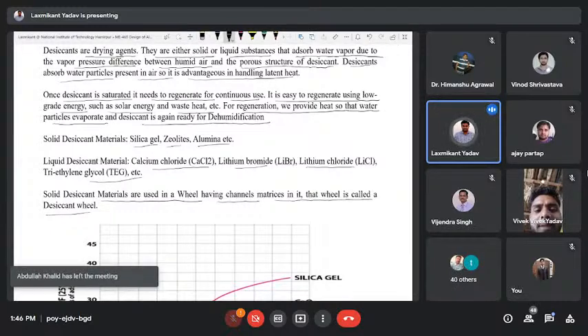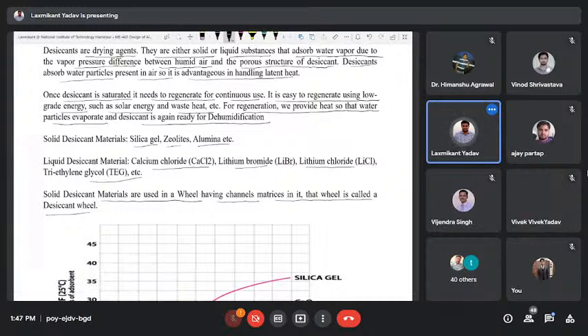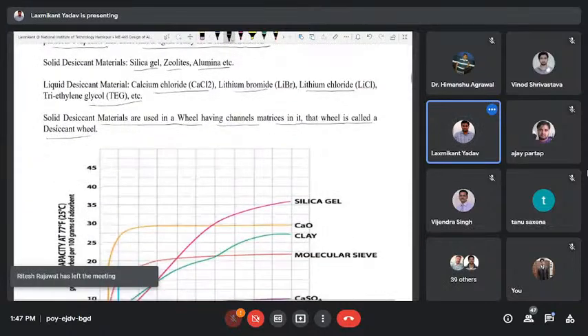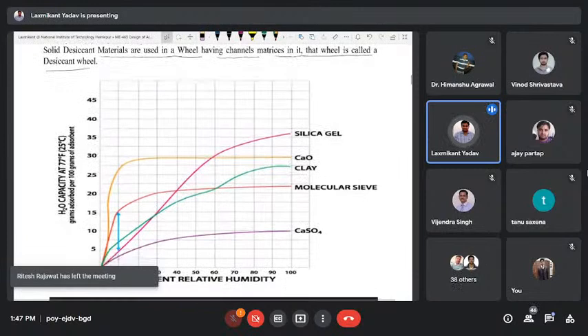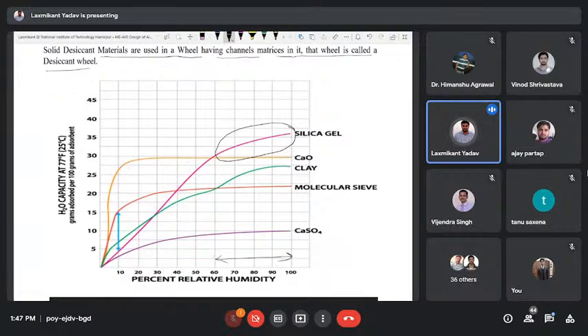Where the desiccant material is deposited on the matrix of that wheel, and we pass the air through the wheel. So it is a continuous phenomenon. So adsorption and regeneration take place simultaneously. Clear? So this is the graph of the moisture removal capacity, the adsorption capacity, of different desiccant materials. We can observe that silica gel has the higher adsorption capacity in the higher relative humidity range from 60 to 100%. So in higher relative humidity, silica gel will perform effectively. However, we can observe that calcium oxide works effectively in the lower relative humidity range from 10% to 60%.